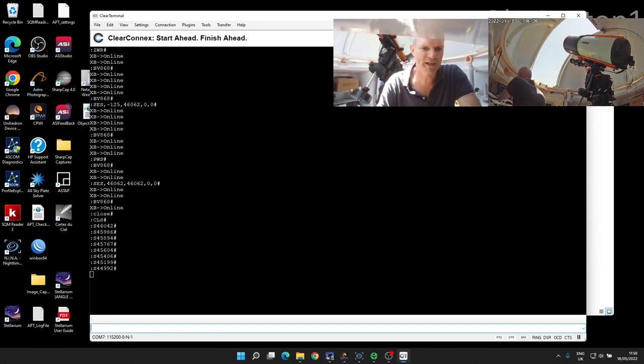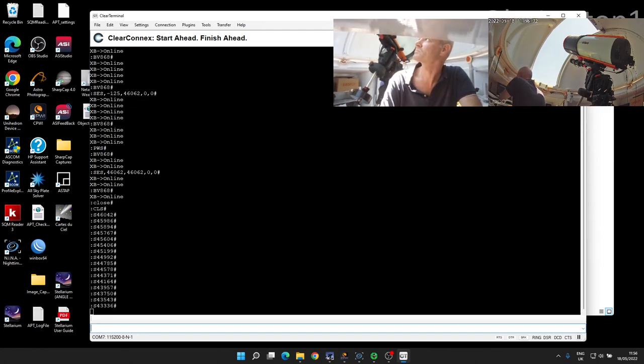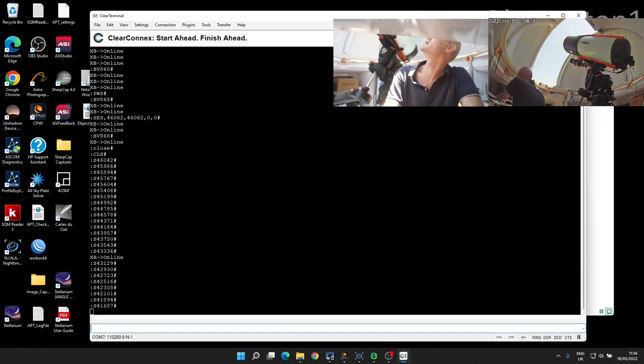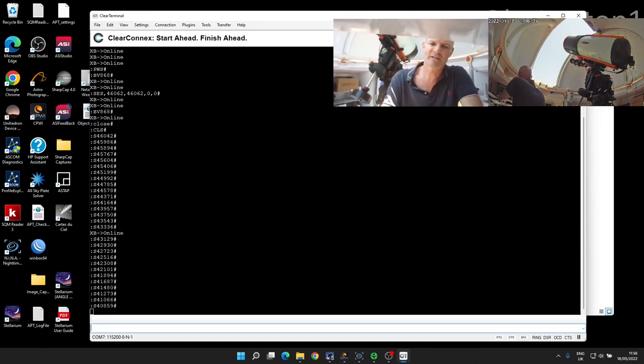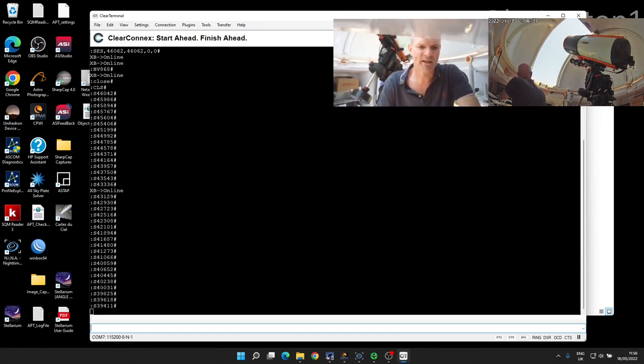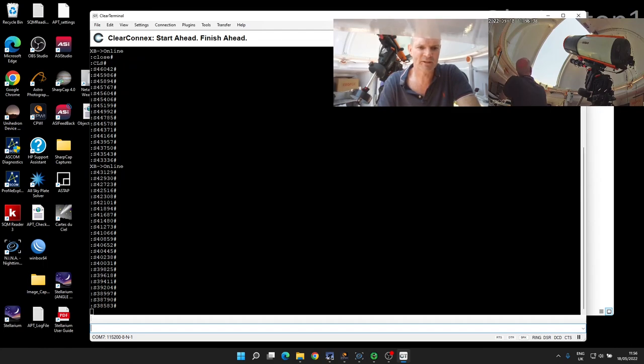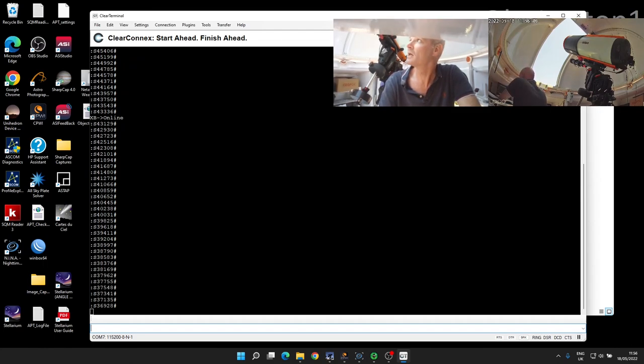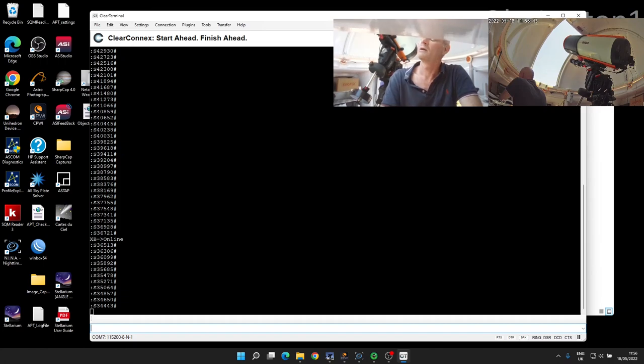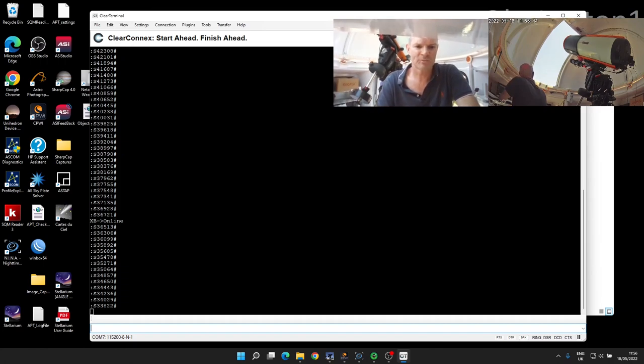You'll see that the shutter starts to drive close. So we've recovered the comms, we put it in a state where it thinks it's open, and now we're driving it to the closed position. So we'll leave that to run.